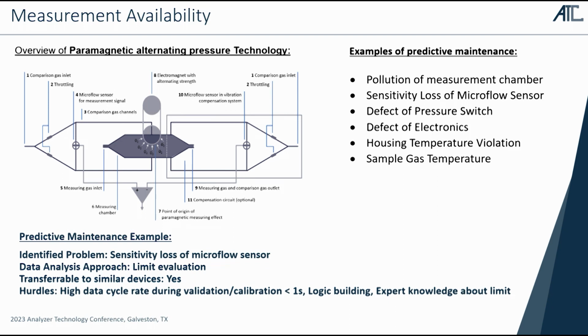So the microflow sensor is actually transferring the cross flow which exists when the sample gas and the reference gas are meeting each other, and is converting this cross flow to the electrical signal in the end. And of course, if the sensitivity is going down, that means that you have a weaker measurement result. So what we have done here is actually to just put in a specific limit. So a very basic approach.